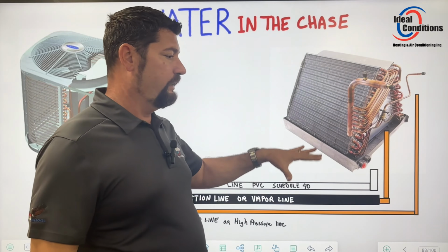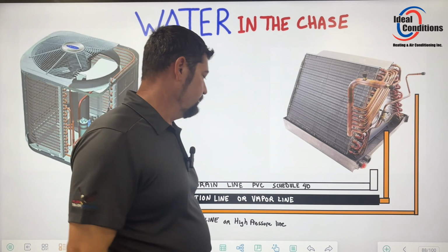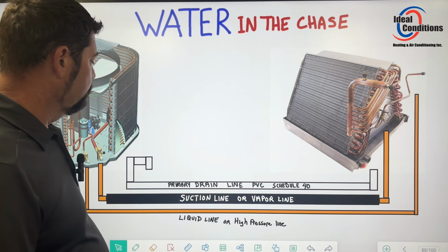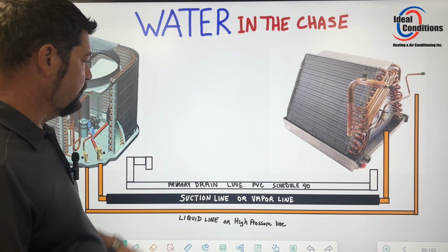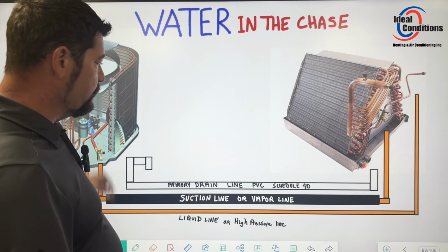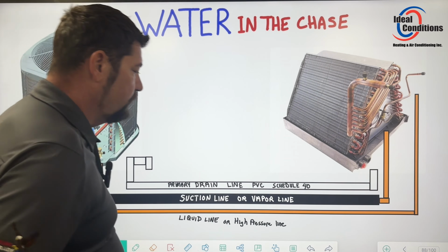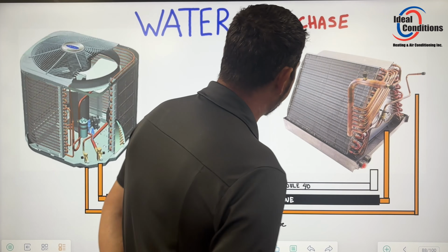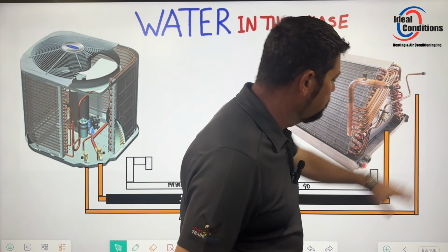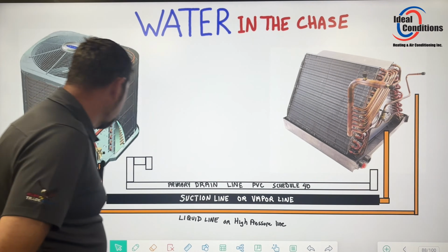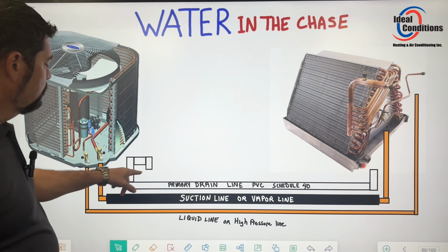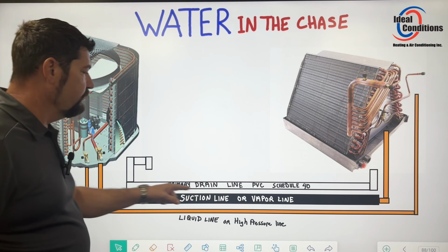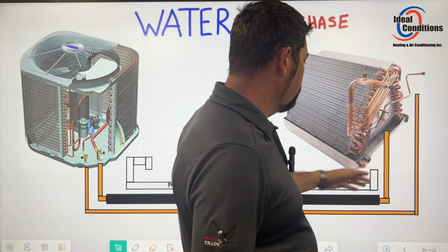Stop looking at the same thing, trying to make sense out of it, right? So pretty simple stuff. These drain lines, if I didn't have any gauges and I just wanted to walk up with my hands behind my back, as an observation, I would say, okay, everything's cold. I can touch the lines. They're cold. Let me go outside. Okay, everything's super cold. I can see that the ground is bone dry. That means my drain line must be building up water and backing up.